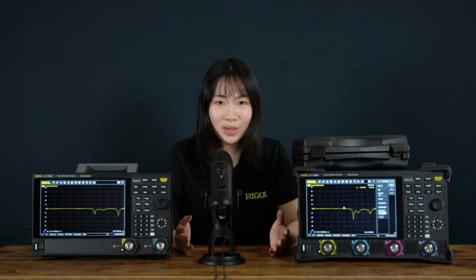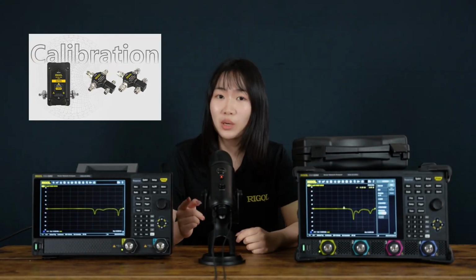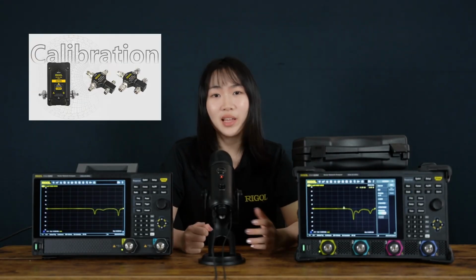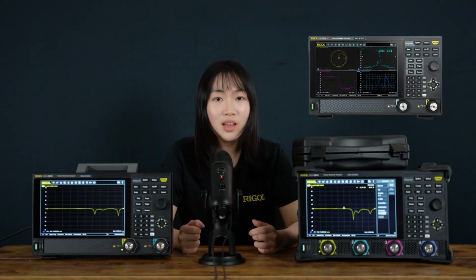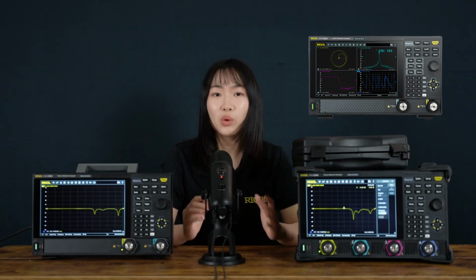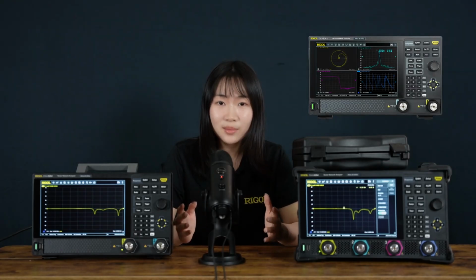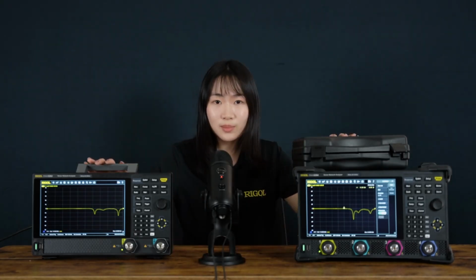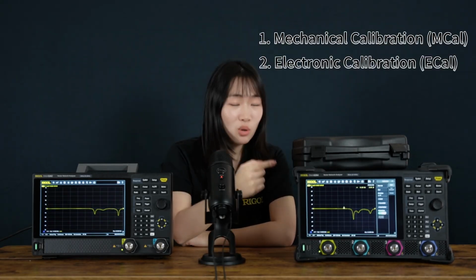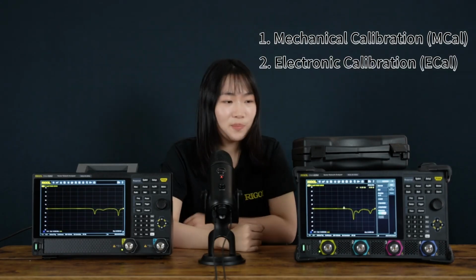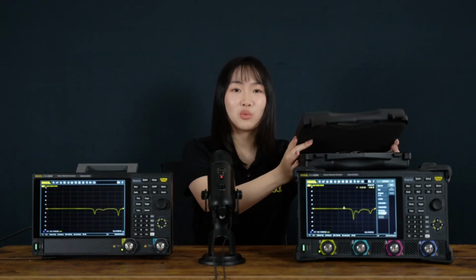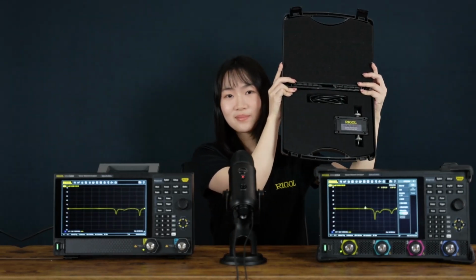So before any real measurements, calibration is one of the most important steps on a vector network analyzer, because it makes your results more trustworthy by moving the reference plane to where your device is actually connected. On these VNAs, you will see two calibration options: the mechanical calibration, or MCal, and the electronic calibration, ECal. Today, I'm going to walk through ECal.